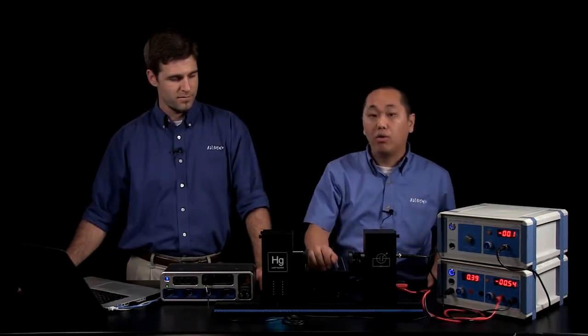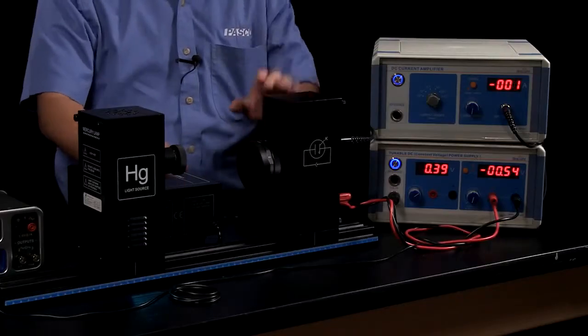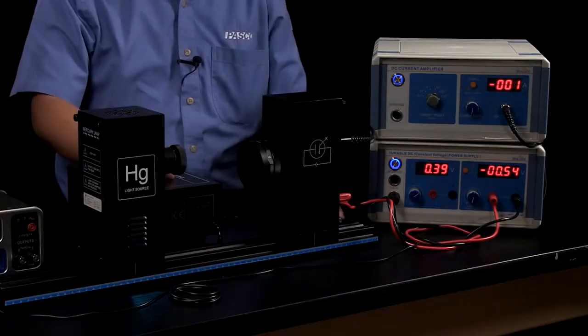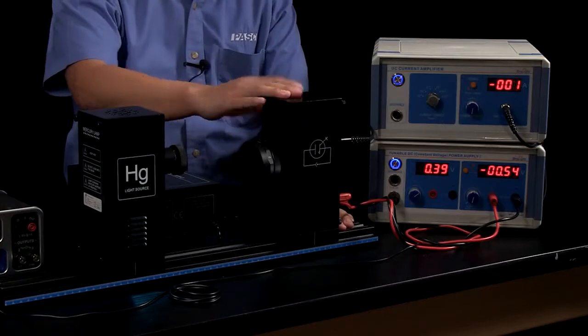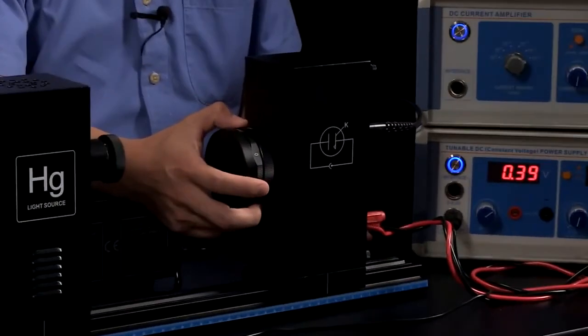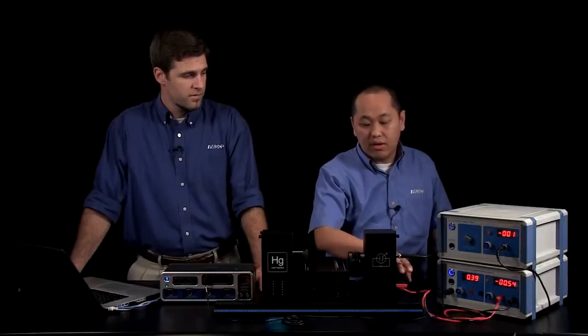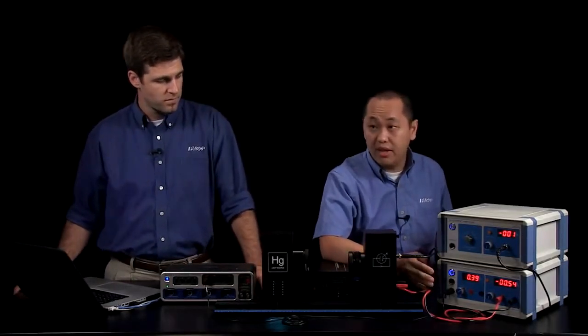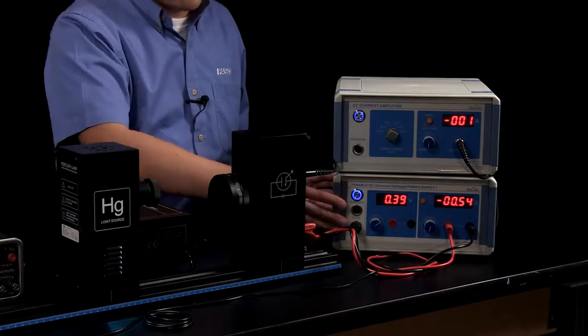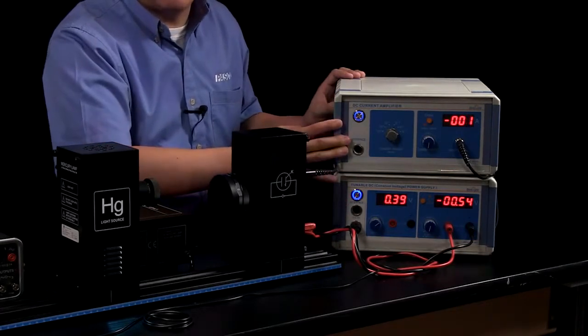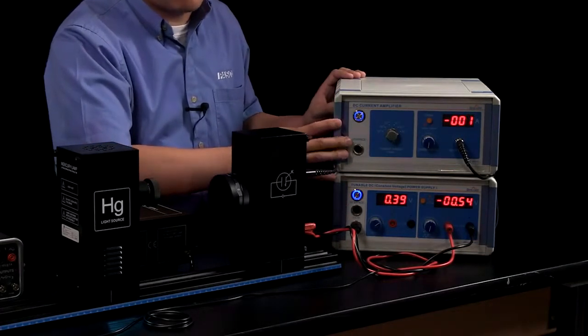Connected on the bottom we have a guide rail that holds together the photodiode and the mercury lamp. On the photodiode itself we have an aperture adjustment and a color filter adjustment and a cover. So connected onto the bottom of the photodiode we have the voltage power supply and then connected on top we have the DC amplifier itself.